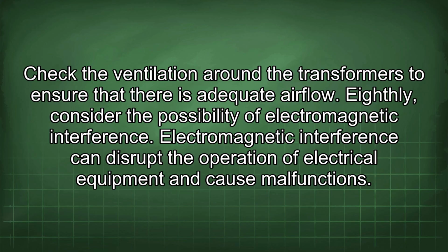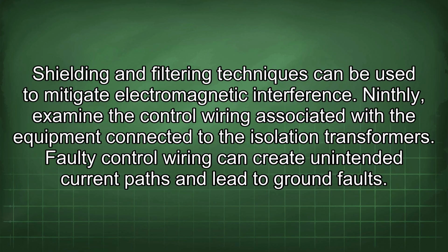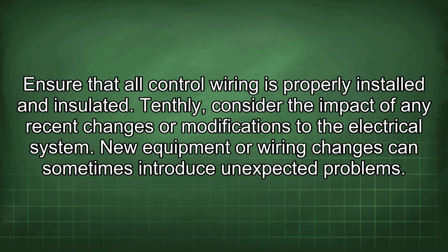Eighthly, consider the possibility of electromagnetic interference. Electromagnetic interference can disrupt the operation of electrical equipment and cause malfunctions. Shielding and filtering techniques can be used to mitigate electromagnetic interference. Ninthly, examine the control wiring associated with the equipment connected to the isolation transformers. Faulty control wiring can create unintended current paths and lead to ground faults. Ensure that all control wiring is properly installed and insulated.